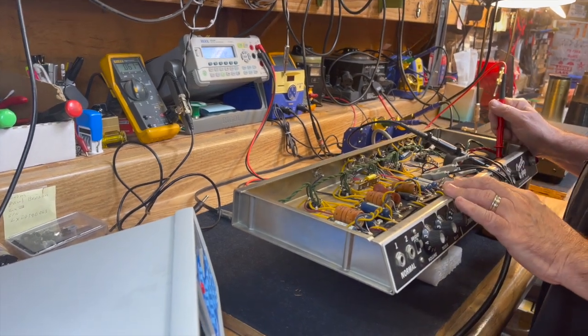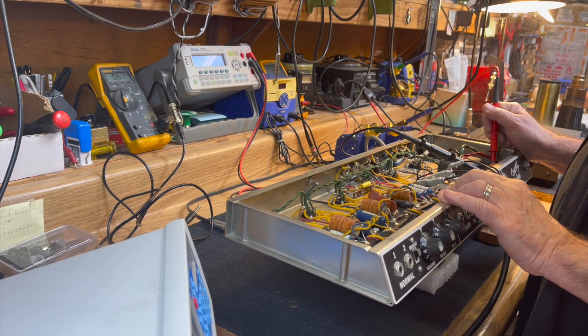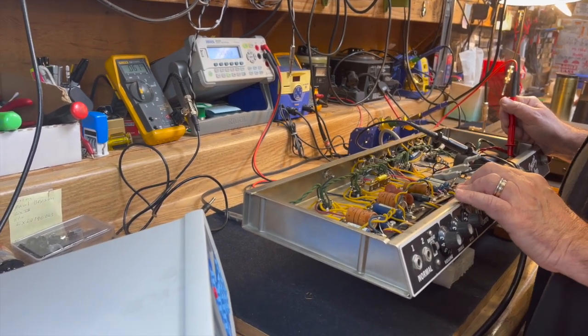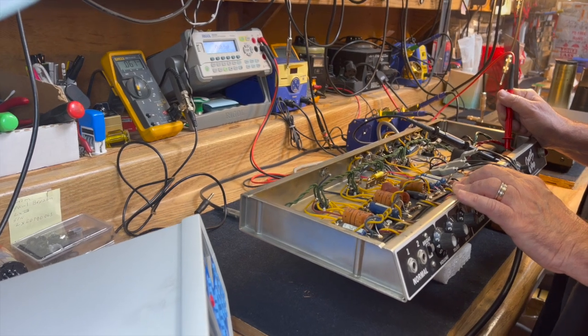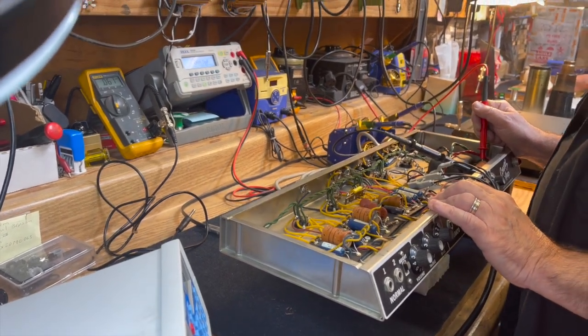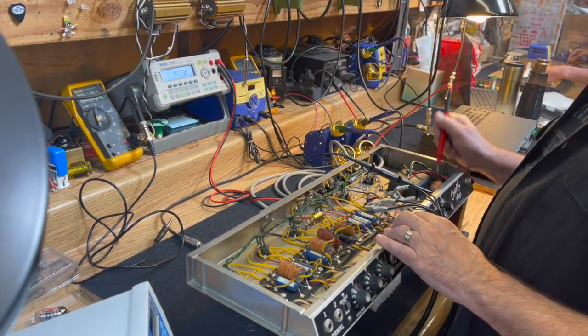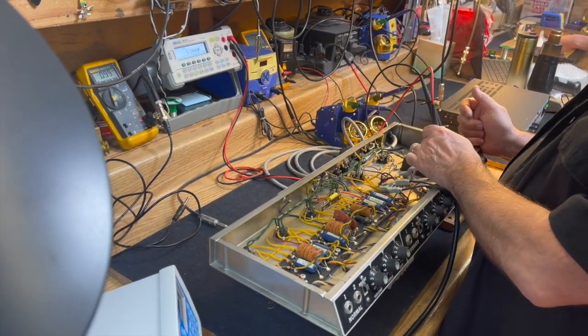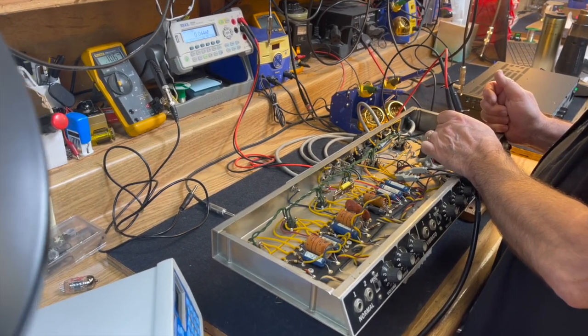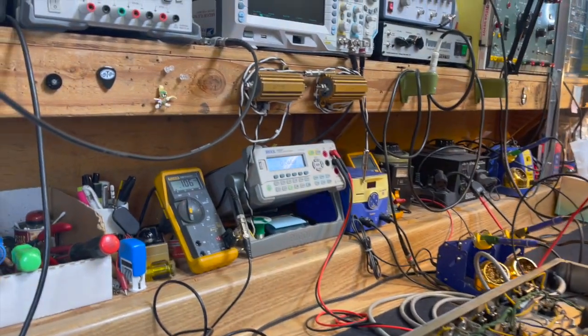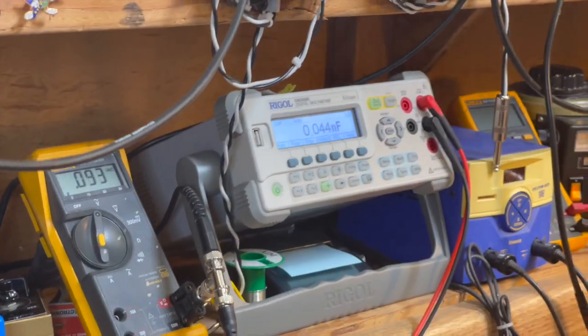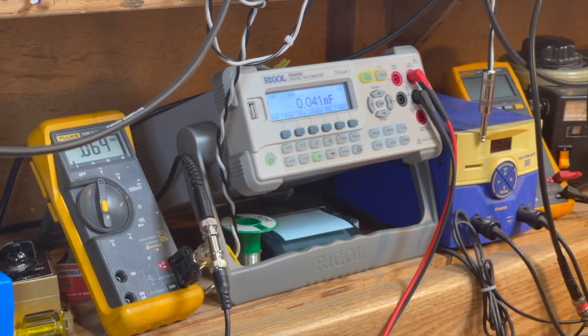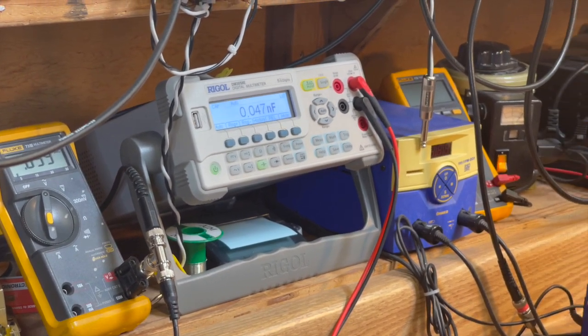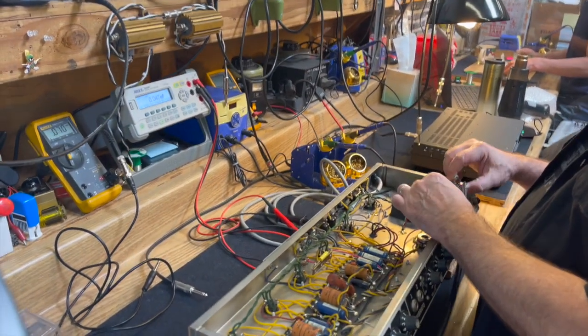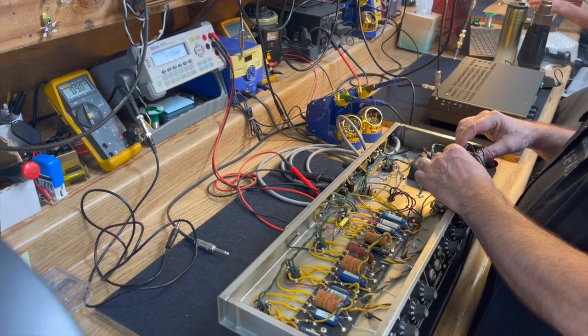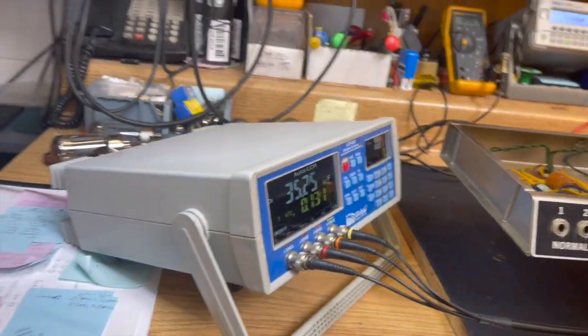So that doesn't mean that this meter is telling me the capacitor is relatively good and that one's telling me it's relatively bad, because it's actually saying that it's got a little more than 2 times, 2.5 times the capacitance that it's rated at, which actually is not a bad thing, it's a good thing. But again, we're testing it in circuit, and that could have a bearing on the reading. If I reverse the polarity on the digital voltmeter, as you can see, we don't get anything. The digital voltmeter is passing a very small voltage through the capacitor to calculate the capacitance value. The LCR meter is also doing that, but in a slightly different way.